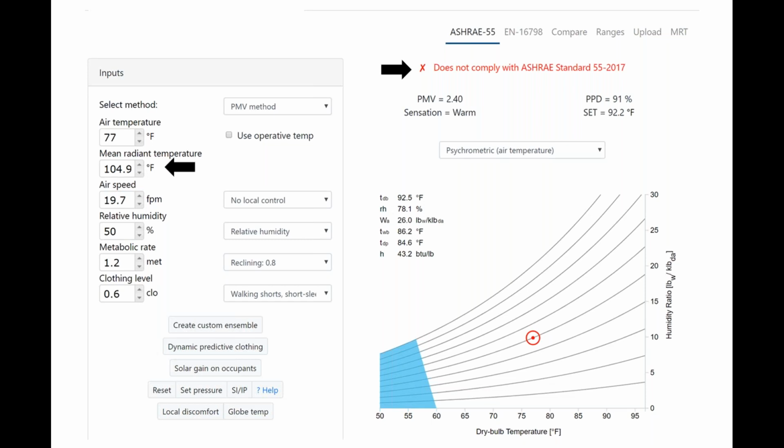So it's incredibly powerful when you're sitting with an architect and the client and everybody else. If you're doing the design charrettes where everybody is sitting around the table with the design professionals, you can draw attention to, well, listen, the beautiful design, the building's very attractive, but you have a lot of windows here, Miss Architect. And the client goes, yes, but we have a beautiful view of the ocean or the mountains or the prairies or whatever it is. And you can say, yes, it is a beautiful view, but if the sunlight comes through and this occupant is in this space and experiences that shortwave radiation, they will not be comfortable, and they will in fact close the blinds.